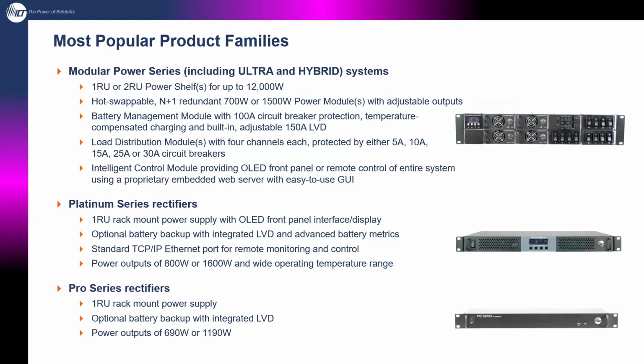For load distribution, you can plug different pieces of gear into our equipment and run, monitor, and control them all individually. They can all be protected with an appropriately sized circuit breaker, anywhere from 5 to 30 amps. But the circuit breakers themselves are almost secondary protection devices—all the settings, disconnects, reconnects, and when loads turn themselves off or on, whether manually or automatically, can be done through our graphical user interface.